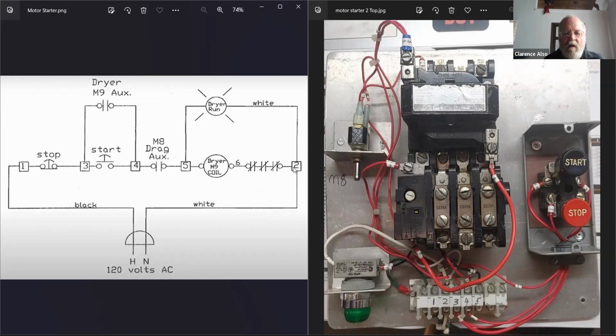Now, how are we gonna prove if our meter is working or not? What do we do with the other probe? Just to see if our meter is working for voltage. You want one on the hot and one on the neutral to see if you got 120 volts. Good job. Okay, so now we know that.